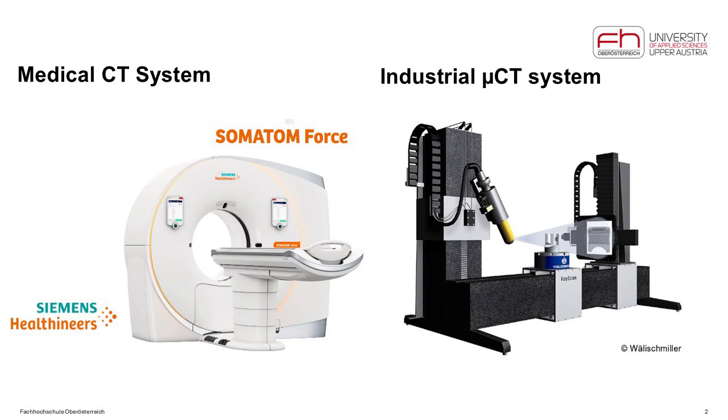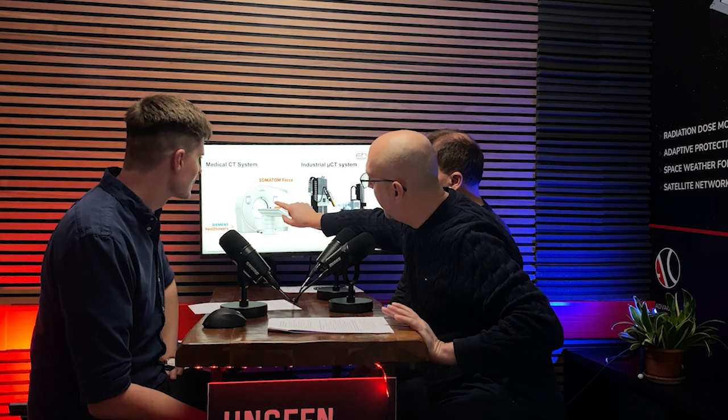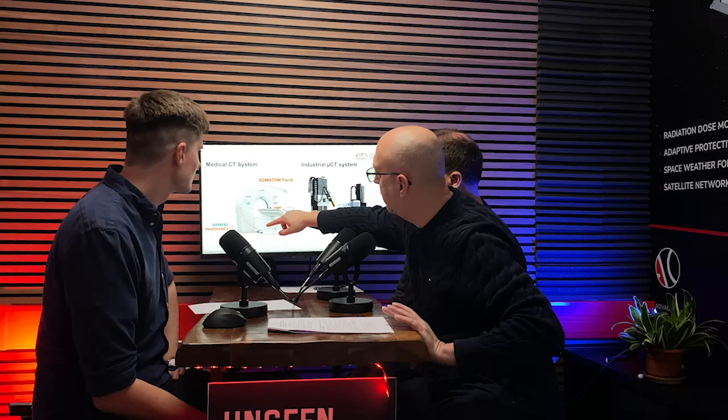Then you have this device. Here the patient is going through. You have 1 or 2 X-ray tubes here in this ring. And then you have a line detector in the outside with depends on the lines. And this one is machinery, one of mechanical engineering machinery, because it's a ton of moving mass, and it spins quite fast in a spiral mode. And in this time, the patient goes through the gantry, and this one is taking single X-ray projection images.